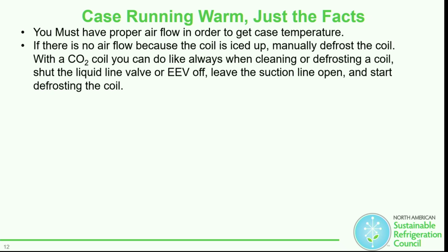When you are pumping the system down, especially on a frozen food case, you could potentially open up the doors to assist in letting that liquid boil out before you start defrosting that coil. If you're manually defrosting a coil, do not just clear the coil and leave. You must find out why it actually iced up.